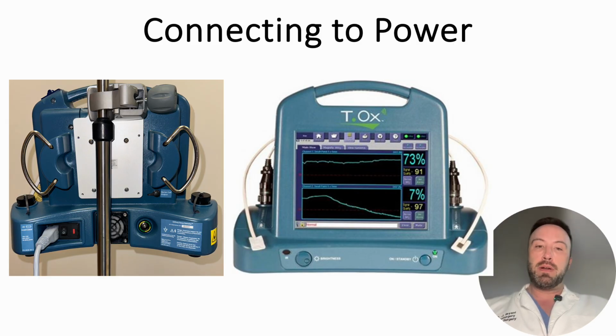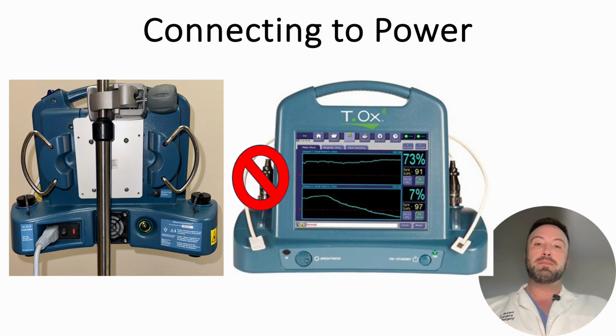At the end of the case, the ViOptix monitor may be unplugged from the outlet briefly for transport, but do not disconnect the sensors from the monitor. The sensor heads are maintained connected at all times to provide continuous monitoring. After the patient has been transferred to the PACU or ICU, be sure to keep the ViOptix monitor plugged into an outlet, as it has very limited battery life and cannot rely on batteries alone.